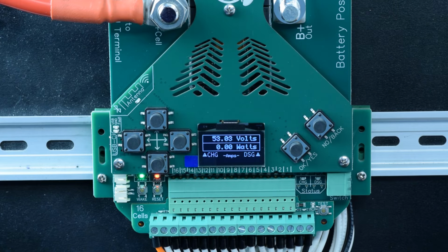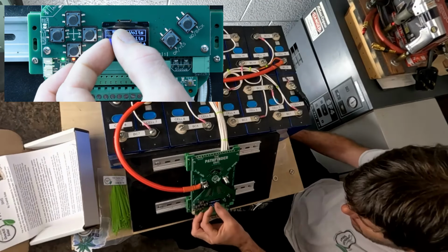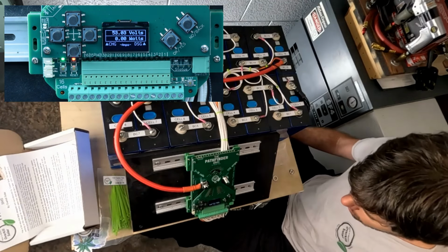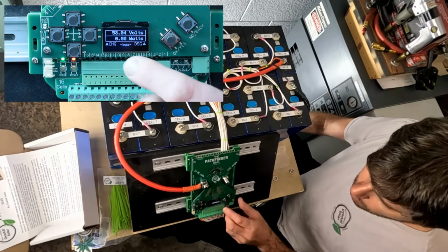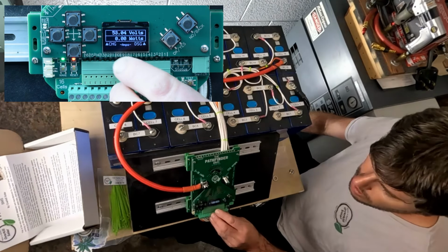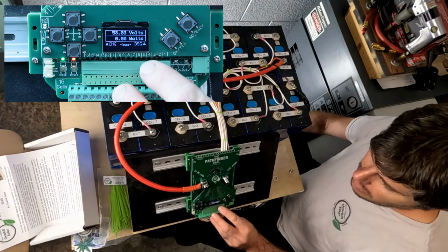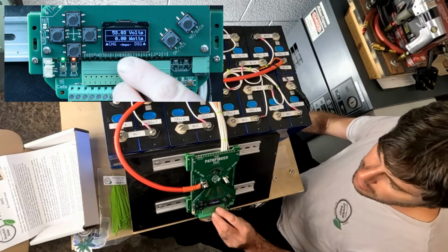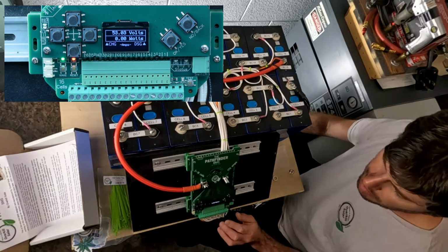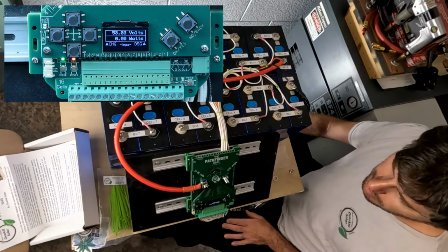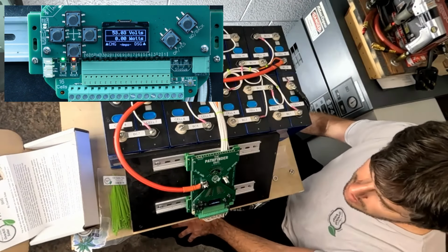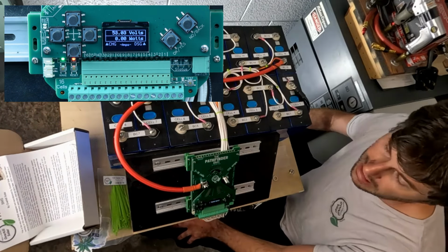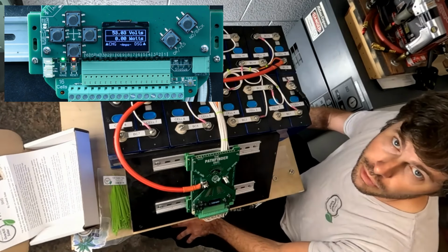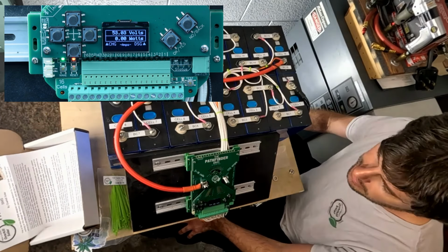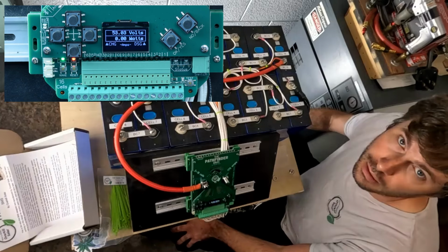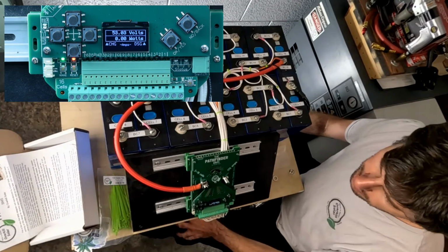Now that it's finished, we have a fresh new screen. We can see the battery voltage, we can see the wattage, and we see no current indicated. Down here where it says amps, if there was any current being measured, we would see a reading there. Having no reading for amperage at this time is perfect, because that means the null current point is calibrated and we don't need to do anything.